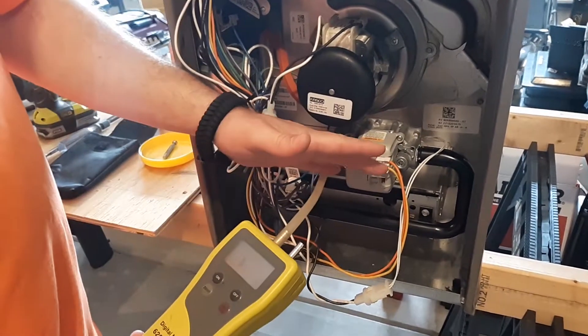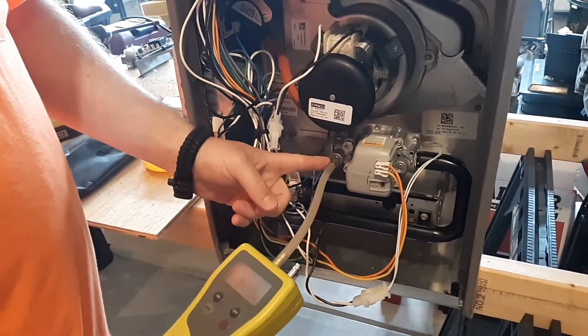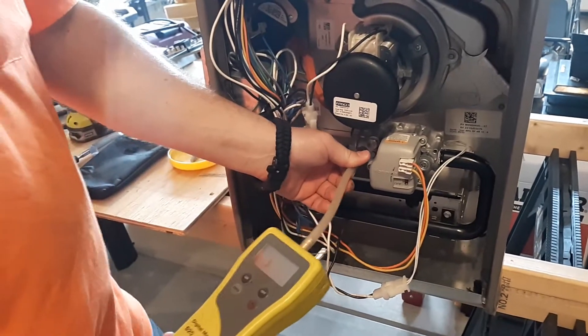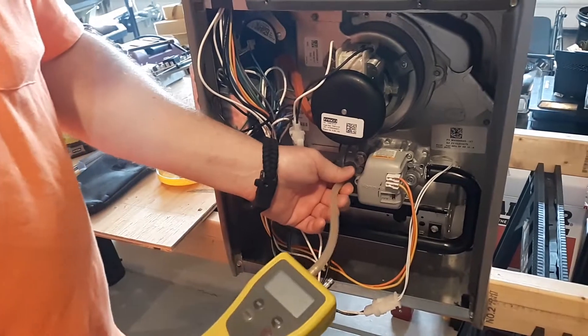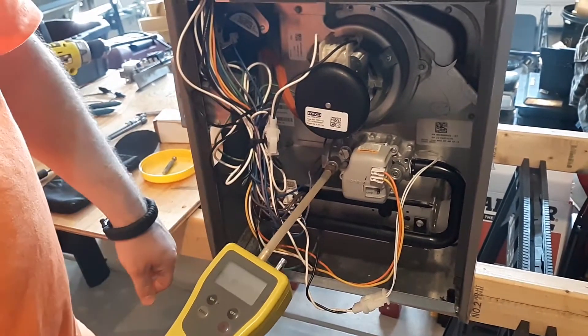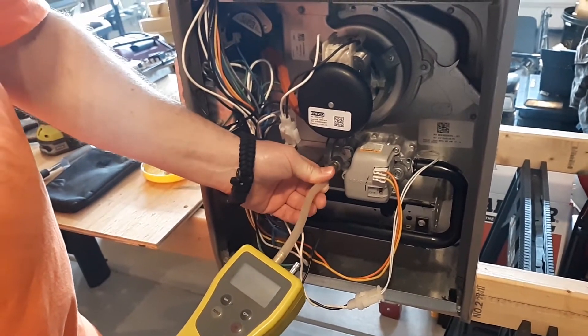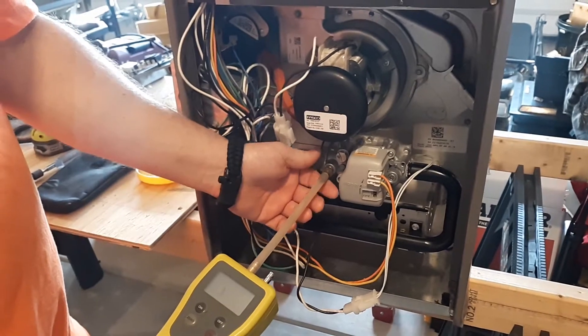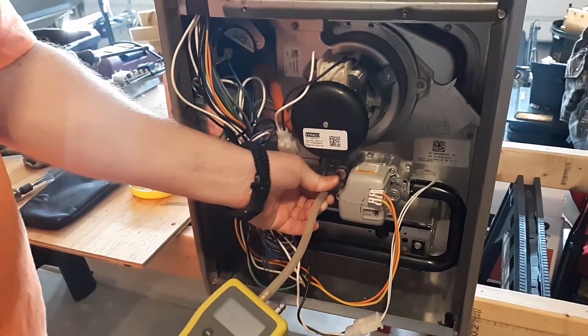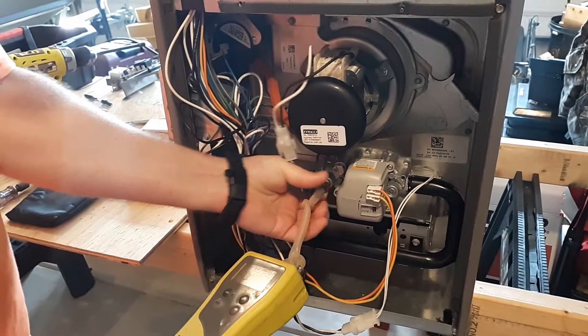You can check the pressure while it's running or when it's static. On the inlet side, you should have upwards of a half psi, or 13 to 14 inches of water column, depending on whether a regulator is there or not. On the outlet, do the same procedure — it will be much smaller: three and a half inches for natural gas or 10 to 11 inches for propane on the manifold side.